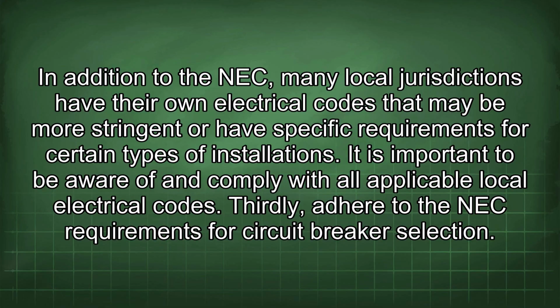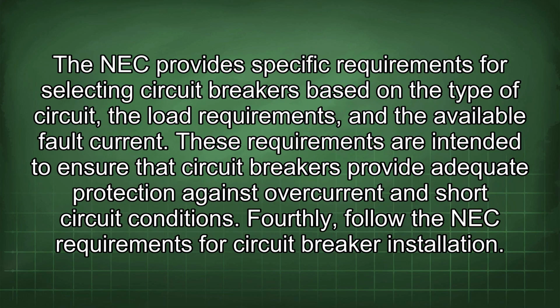Thirdly, adhere to the NEC requirements for circuit breaker selection. The NEC provides specific requirements for selecting circuit breakers based on the type of circuit, the load requirements, and the available fault current. These requirements are intended to ensure that circuit breakers provide adequate protection against overcurrent and short circuit conditions.